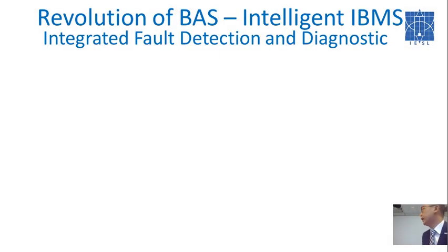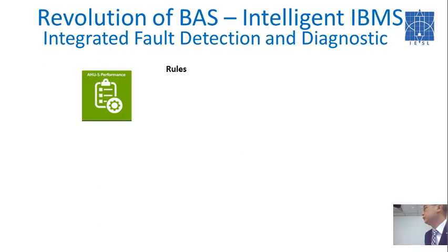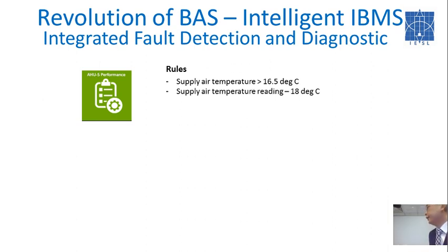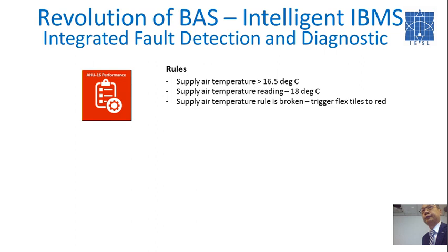Here's another example of IFDD. I can write rules for AHUs—for example, if the supply air temperature for the AHU is greater than 16.5, it creates a warning. Currently the supply air temperature is at 18 degrees, so the green flex tile—we call these flex tiles—will turn red. As a building technician, I might not know how to check, but with the assistance of the checklist, I click on the flex tile.